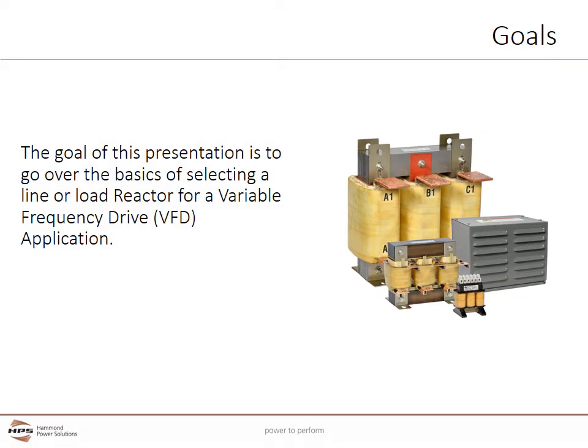The goal of this presentation is to go over the basics of selecting a line or load reactor for a variable frequency drive, also known as a VFD application. VFDs are used to control the speed of an AC motor by simulating different frequencies, and frequency determines motor speed. The discussion will focus on basic applications involving standard AC induction motors. If there are any questions on your application, please don't hesitate to call HPS.